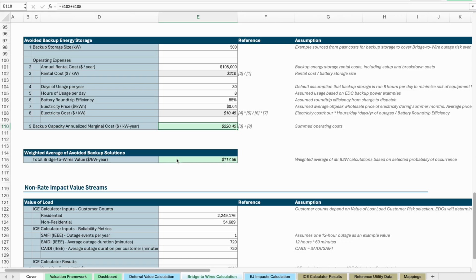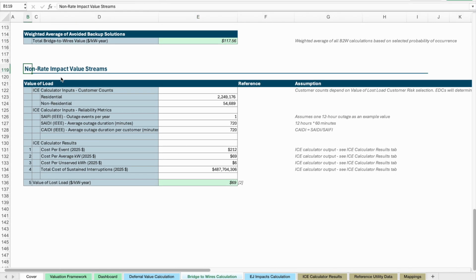For the rate impact avoided backup solutions, we weight these based on inputs that I'll return to at the top to calculate a weighted average bridge-to-wire solution value. For the non-rate impact value stream, we calculate the value of lost load. This valuation pulls from the DOE's interruption cost estimate, or ICE calculator, which is referenced in a later tab in this workbook. The key inputs to this calculator are the customer counts and reliability metrics. These are not active user inputs, but predetermined based on the economic risk profile for customers served by the bridge-to-wires asset. Basically, the overall value customers are expected to place on avoiding an outage.